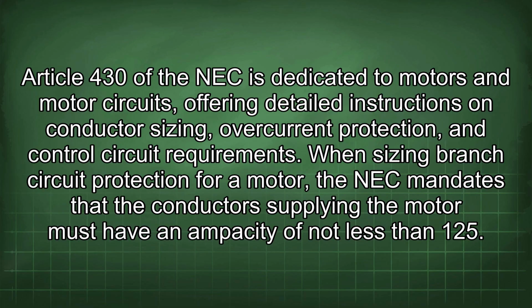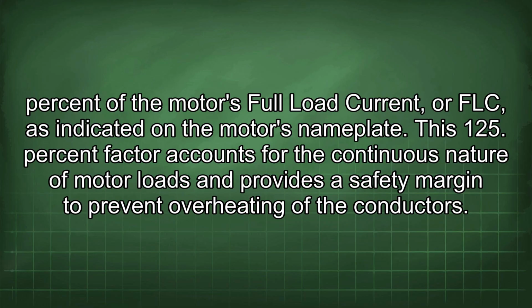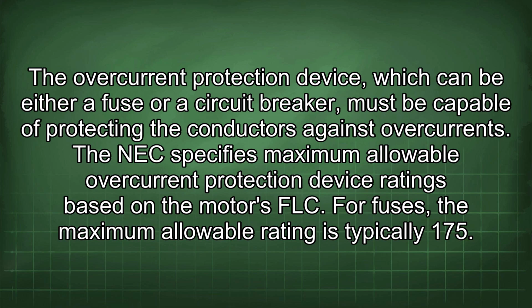Article 430 of the NEC is dedicated to motors and motor circuits, offering detailed instructions on conductor sizing, overcurrent protection, and control circuit requirements. When sizing branch circuit protection for a motor, the NEC mandates that the conductors supplying the motor must have an ampacity of not less than 125% of the motor's full load current, or FLC, as indicated in the motor's nameplate. This 125% factor accounts for the continuous nature of motor loads and provides a safety margin to prevent overheating of the conductors. The overcurrent protection device, which can be either a fuse or a circuit breaker, must be capable of protecting the conductors against overcurrents.